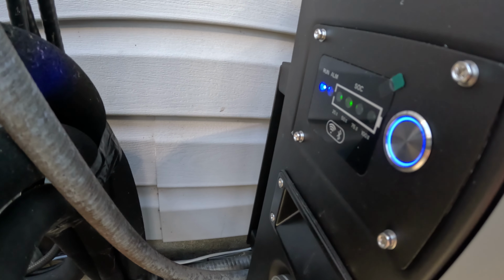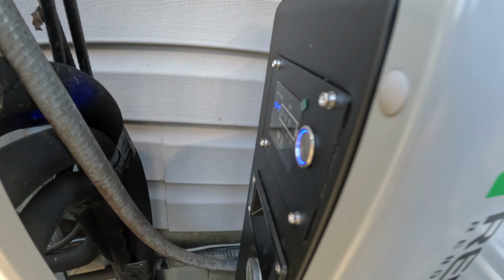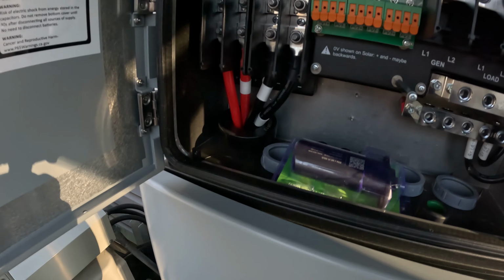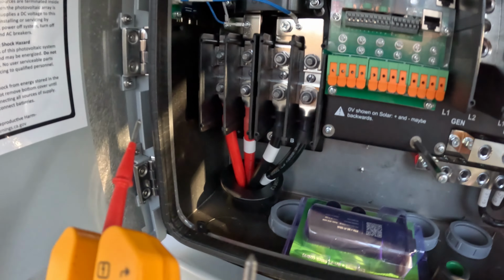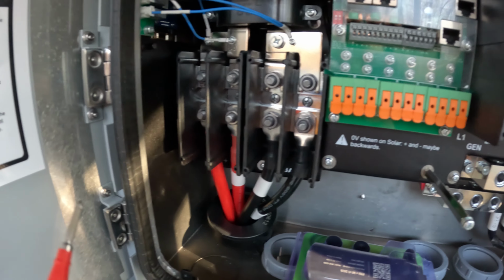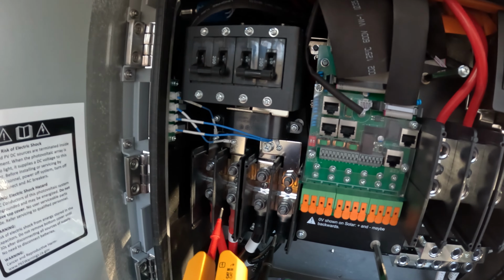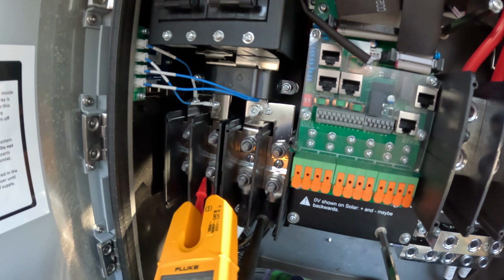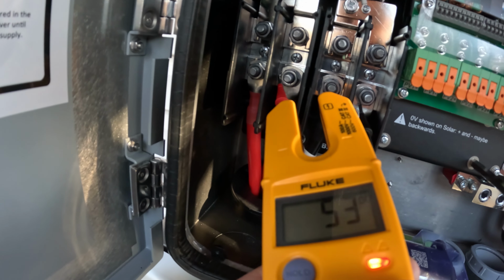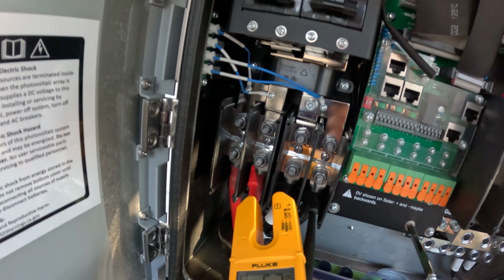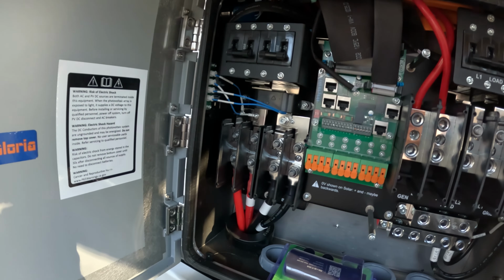We've got our power switch turned on the battery bank, so we're going to come up here and check voltage at the lugs. Breaker is still off. So we've got 53 volts DC incoming. So we're good there.